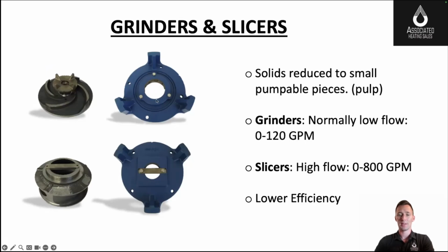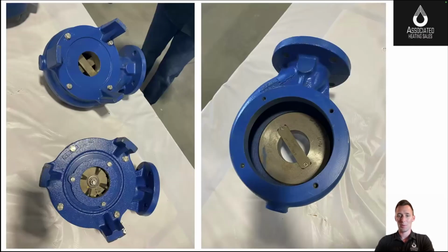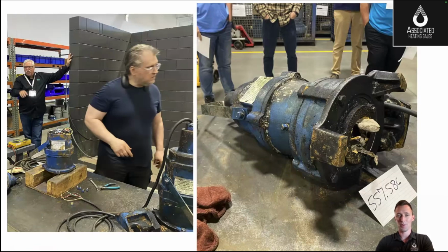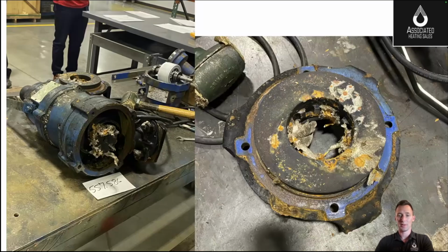This might be nice in a residential application where you have complete control over what's being flushed and you're never going to flush a wipe or a hygiene product that shouldn't be flushed. But in the commercial application, this is most often what we see. The smaller grinder pumps will wrap up on the hygiene products and really burn up pumps quickly as soon as it's there. I mean, it sort of relies on momentum as well. So when something's wrapped in there, the pump tries to turn on, nothing spins, the motor heats up and burns up rather quickly.